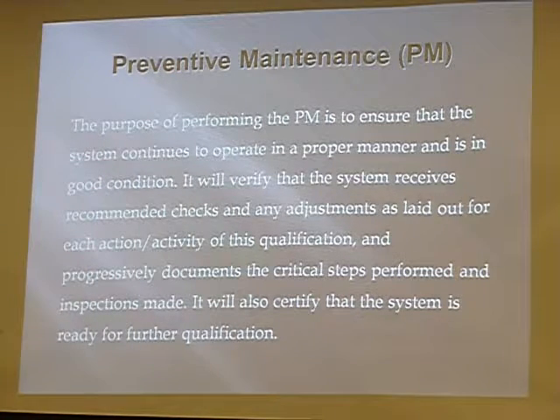Preventive maintenance. The purpose of performing the PM is to ensure that the system continues to operate in a proper manner and is in good condition. We'll verify that the system receives recommended checks and any adjustments as laid out for each activity in this qualification, progressively documenting the critical steps performed and inspections made. We'll also certify that the system is ready for further qualification. Typically, we go out every 6 months.